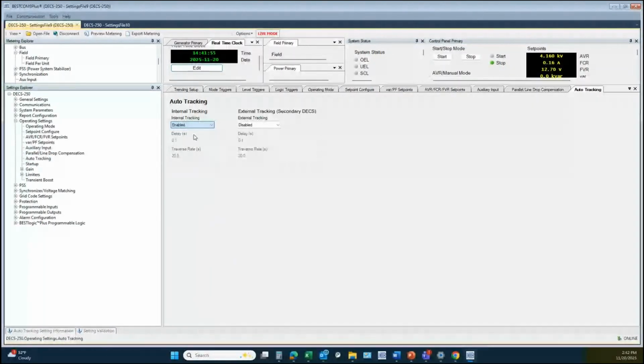Auto tracking, this we typically recommend having enabled. The auto tracking allows the non-active modes of operation to track what's actually occurring while you're regulating in whichever mode is active. So if you're in AVR control regulating at your nominal voltage and it requires 6 amps of field current, your FCR control mode will track to that 6 amps of field current. If you then lose the ability to sense voltage or decide to transition from AVR control to FCR control, you could make that transfer and it would be essentially a bumpless transfer. There's actually a null balance LED on the face of the unit to let you know when the non-active modes have tracked to what's actually occurring while you're regulating, to let you know that it is safe to go ahead and transfer if you choose to do so.